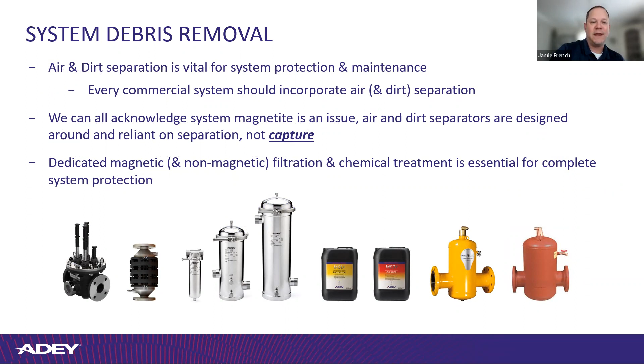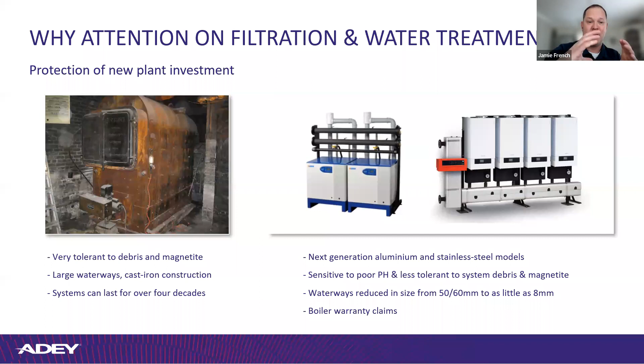And here's why. We're used to, back in the day, the big cast iron boilers where you could pretty much bowl inside of that fire tube, right? I mean, it's huge. The passageways are just very tolerant to any sort of debris in the system, but not very efficient either. So as we push for efficiencies, we start looking at the stuff on the right, or those rack systems or staged boilers, and they're typically aluminum or stainless steel, very sensitive to water quality, and their passageways are down to 8 millimeters. So we're talking big honking passageways to little tiny ones.